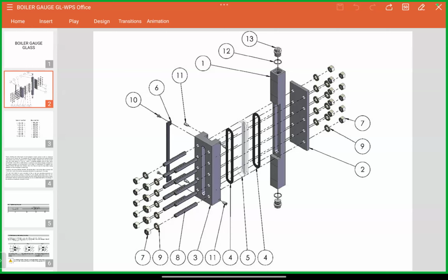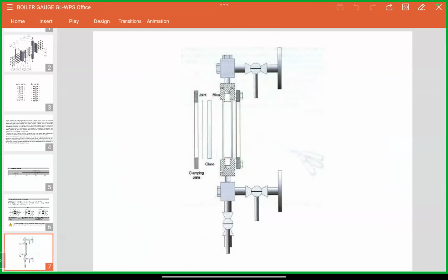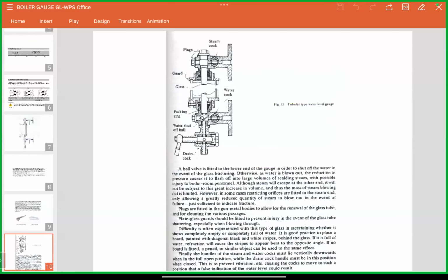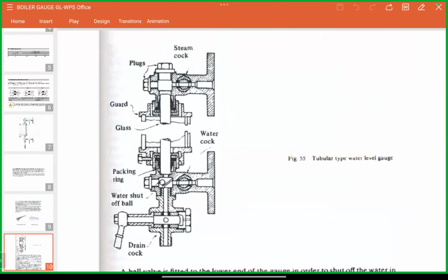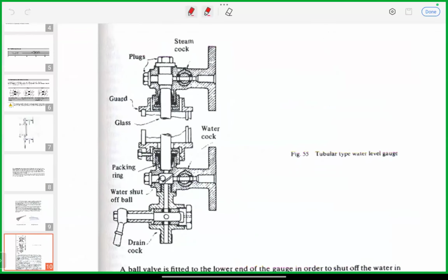Different gauge glasses are available in the market. Depending upon the capacity and working pressure of your boiler, multiple different types of gauge glasses can be installed. For example, tubular type of gauge glass, generally applicable for very low pressure boilers.